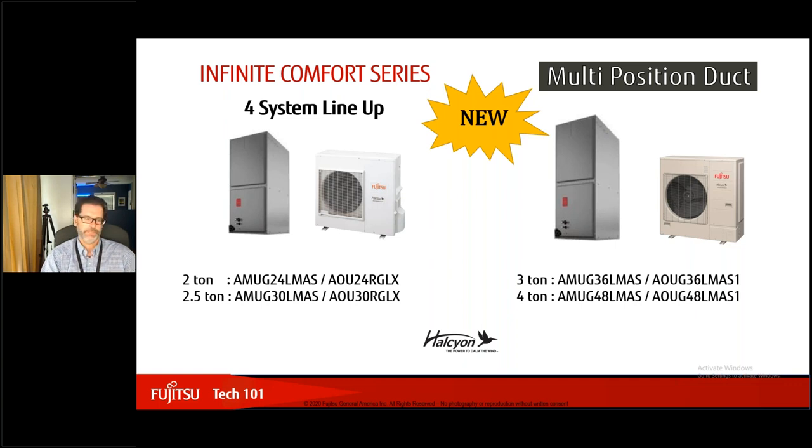So that really is gonna cover a lot of ground. In some of these larger homes, I've seen people fail because they took our low static, or ARU, or mini duct air handler, and they don't understand what the blower's capabilities are. They look at tonnage and they took this one out and put that one in, let's say a 2-ton, and they don't realize the static pressure is quite low and then they're not delivering comfort. So they kind of shot themselves in the foot. It was a hard learn, and I hope I've helped people come up with solutions. It's basically adding another system.